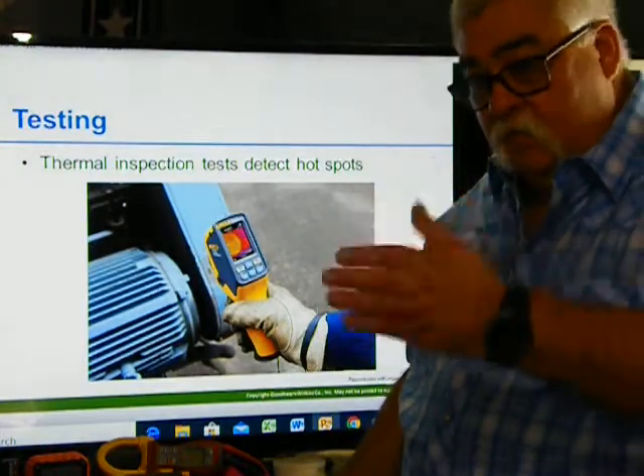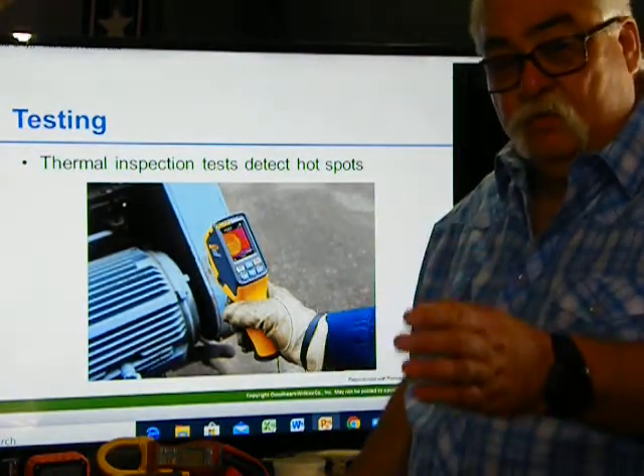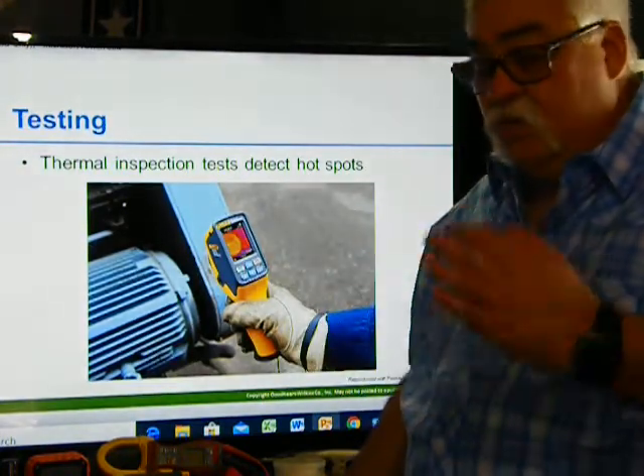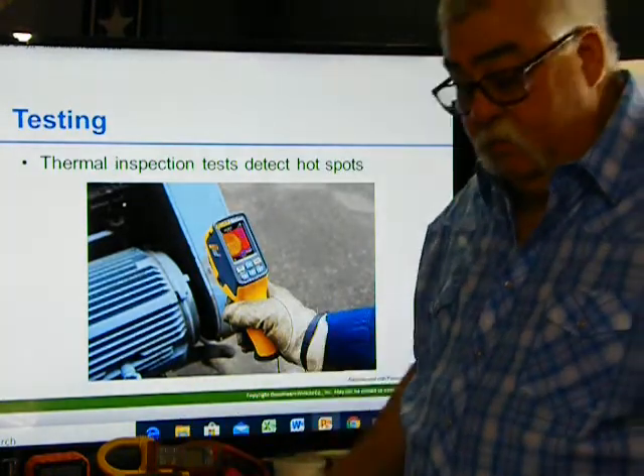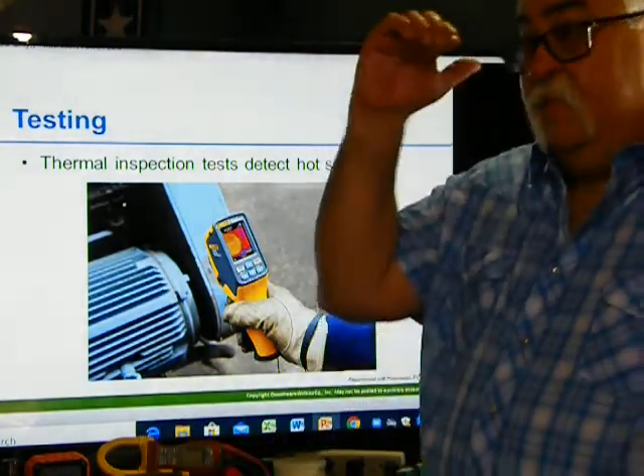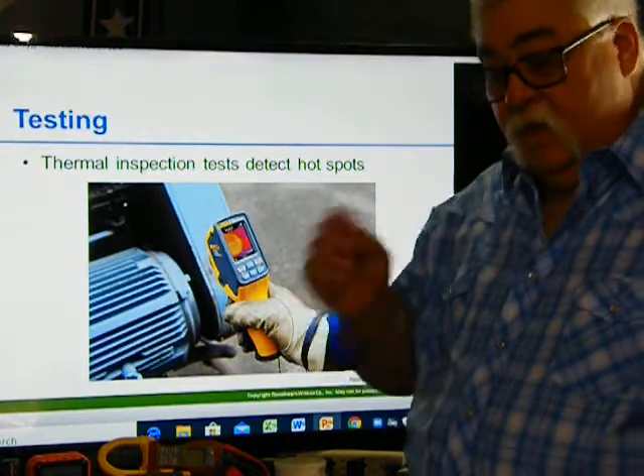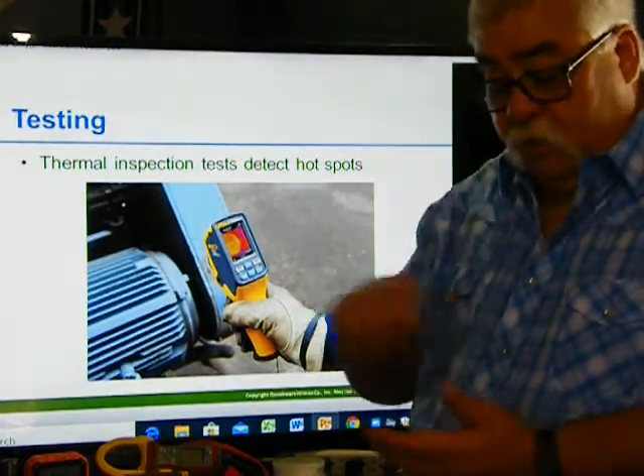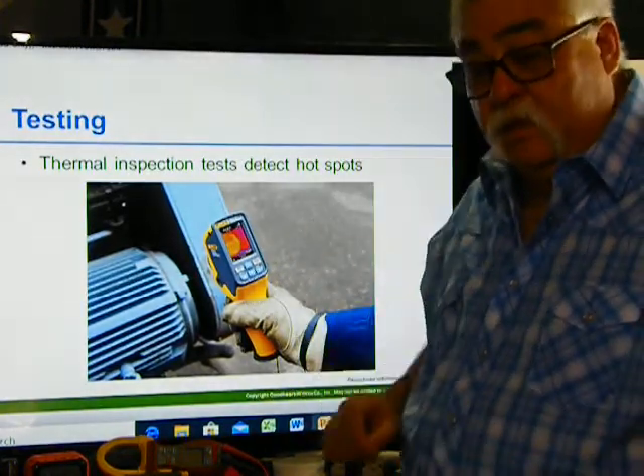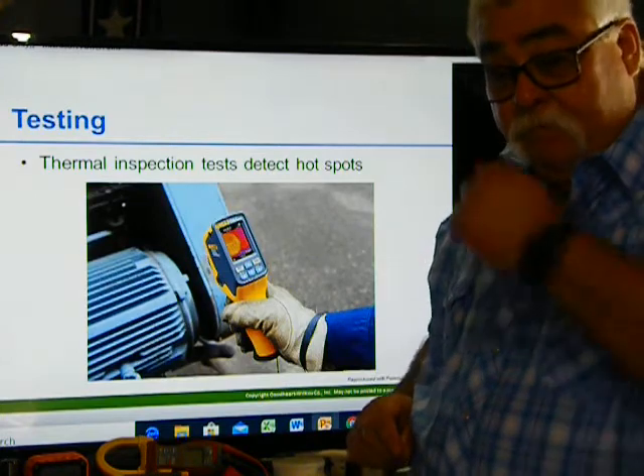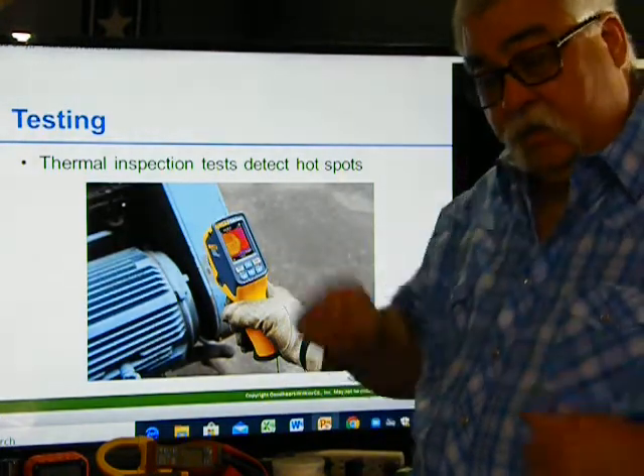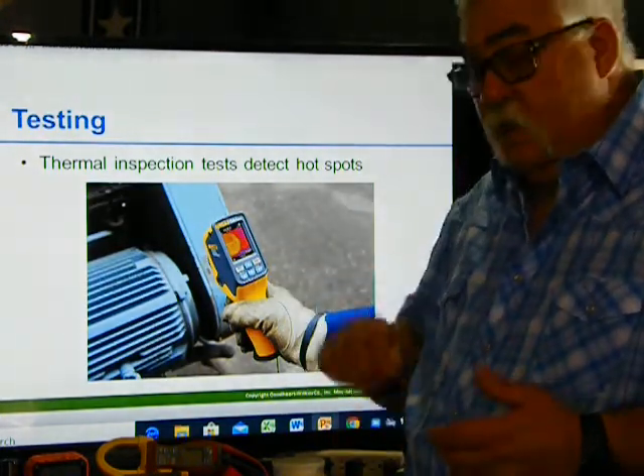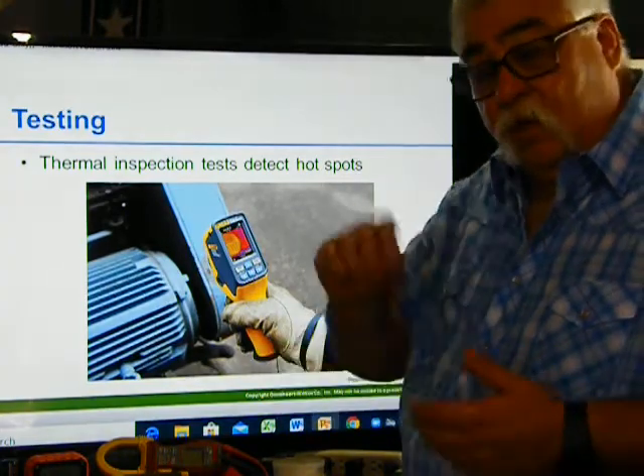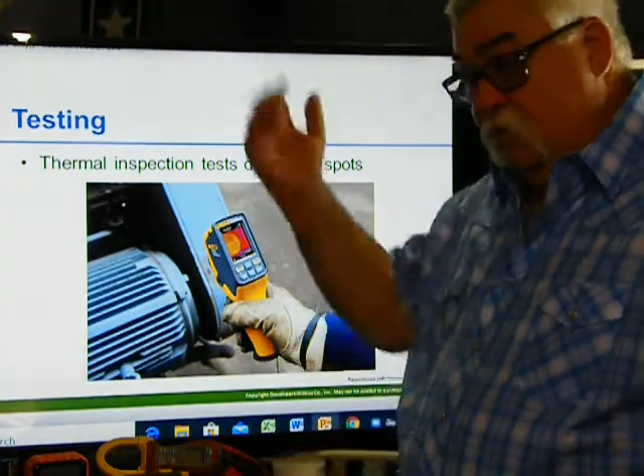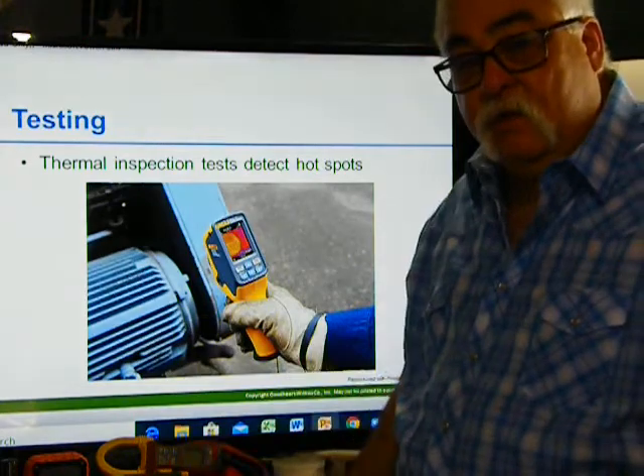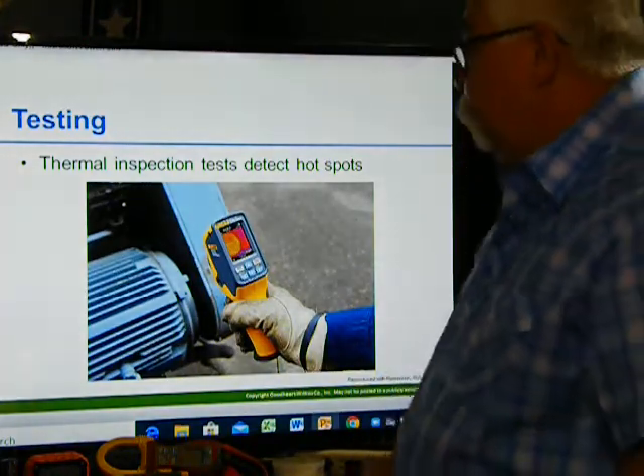So I would pick 1 week, 2 weeks. 1 week I'd do 2 floors, another week I'd do another 2 floors, or whatever it was, because I had to do this every month. Okay, get my infrared camera, take a recording, get my recording. If I found any hot spots, I had to go back to the book and sit down and write it in the book. Same thing with the GFIs. I'd go in there and I said, okay, fine. I tested this room, this room, this room, and then I had to change them out in certain rooms. All that had to be logged. Why? Somebody from the hospital would come down. They had to make sure that the preventative maintenance was being met.